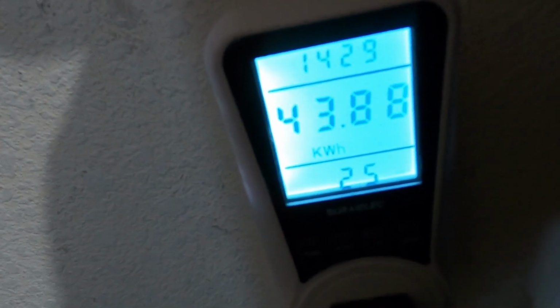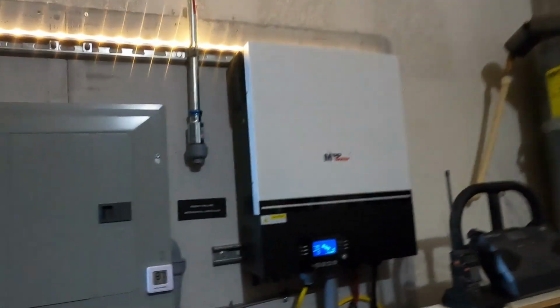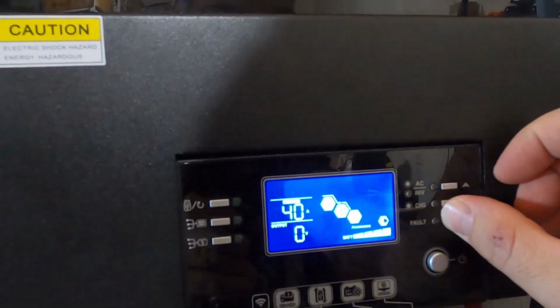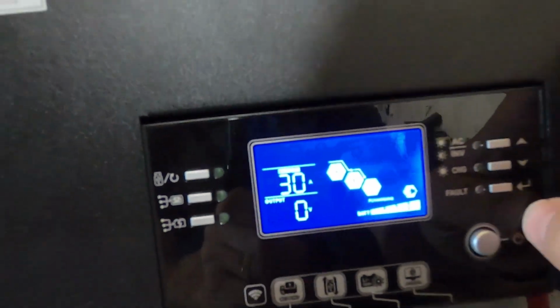and I got my watt meter plugged in, so we can see what we're actually pulling when we're pulling 40 amps of charging current. Oh yeah, we're right at almost 2400 watts. So yeah, I think 40 amps is a little too much. We'll change this down to 30. Okay, now we're pulling 30 amps, and we're at 2000 watts on the outlet.